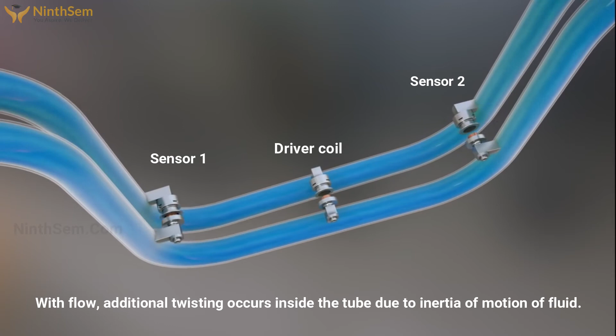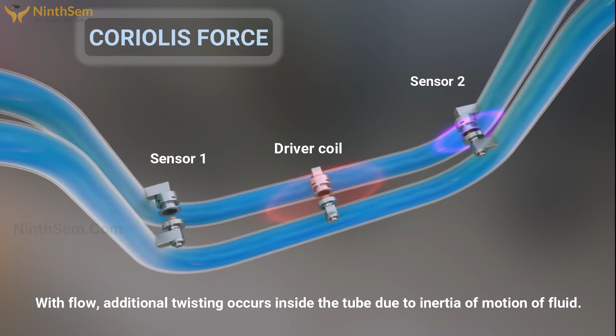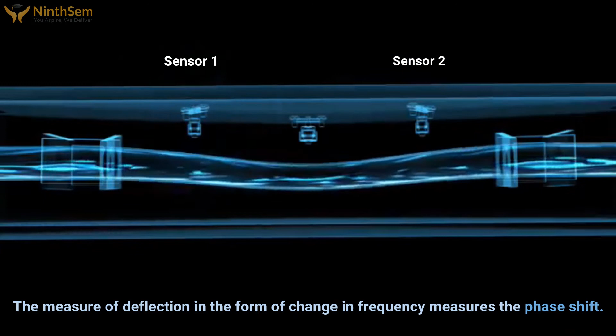When the fluid is allowed to flow inside the measuring tube, what will happen? Additional twisting occurs inside the tube due to the motion of inertia of the fluid. Due to this, Coriolis force is generated. Due to this Coriolis force, the inlet and outlet of the tube oscillate differently. That means the inlet and outlet of the tube oscillate in different directions at the same time, as you can see in figures 2 and 6. The sensors used are very sensitive to pick up the change in the tube oscillation in terms of time and distance. This is the measure of deflection in the form of change in frequency, which is a measure of phase shift.